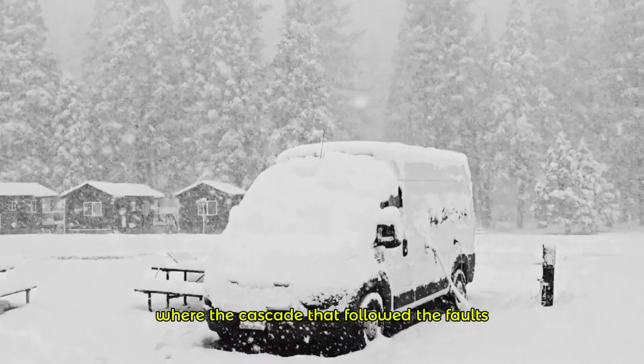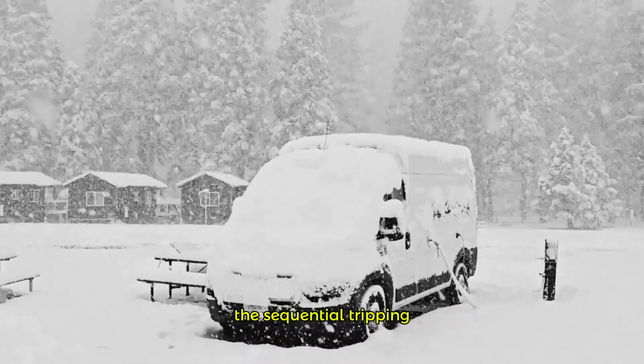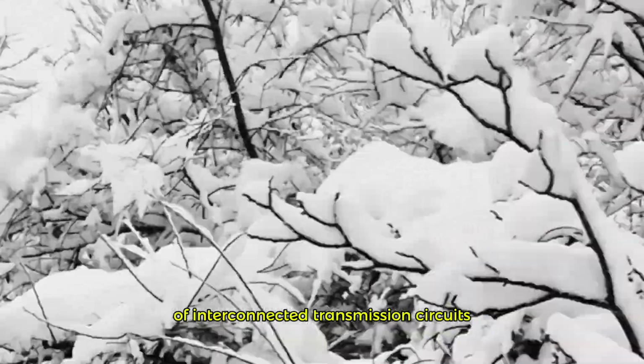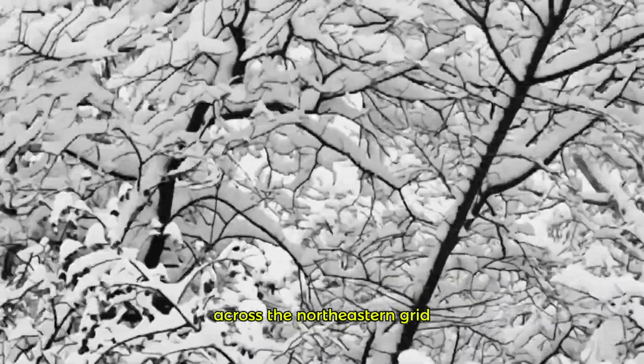But the cascade that followed the faults, the sequential tripping of interconnected transmission circuits across the northeastern grid, demonstrated that a transmission failure in one location can propagate through thousands of miles of interconnected infrastructure within seconds. The grid's interconnection, which is the feature that allows power to move from generating stations to distant load centers, is also the mechanism that allows a local fault to become a regional outage. Those two properties cannot be separated.